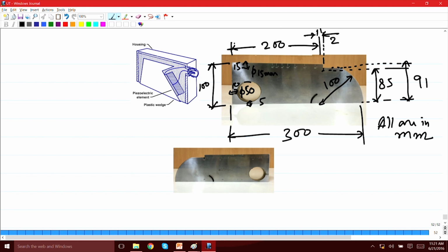So these are the typical dimensions of this block, and now you can see there are several features on it. The first one is the curvature over here, this 100 mm radius curvature. Then, as I said, there are two holes: one over here which is 1.5 millimeter, and then a bigger hole which is a through hole, 50 mm in diameter. Let us see how this can be used to calibrate angle probes.